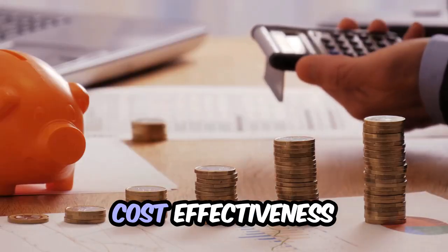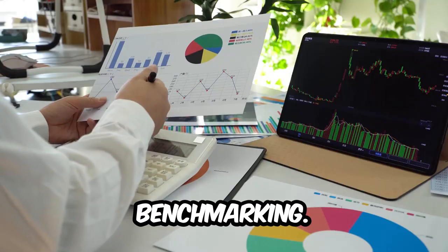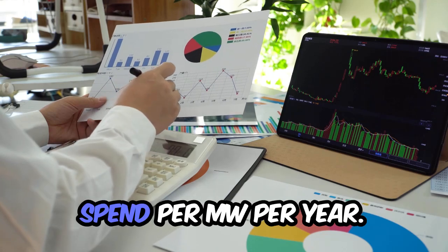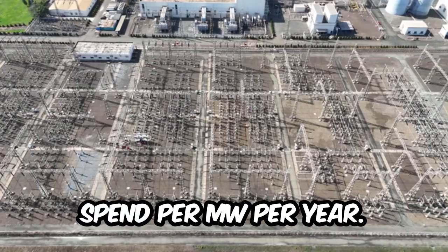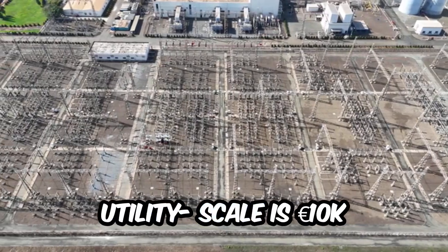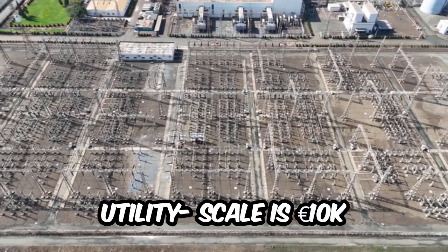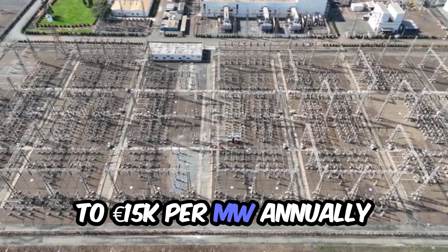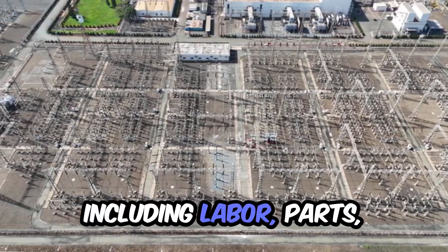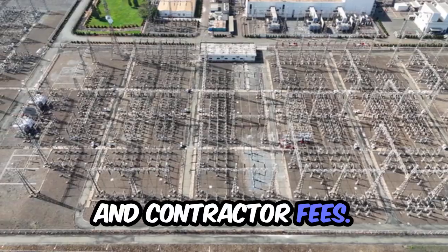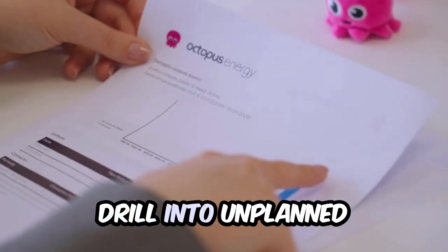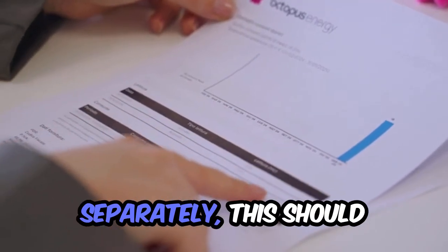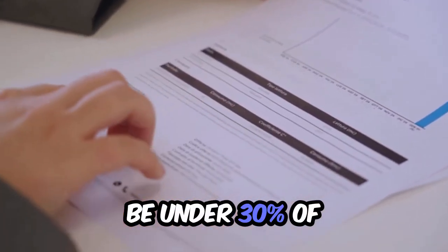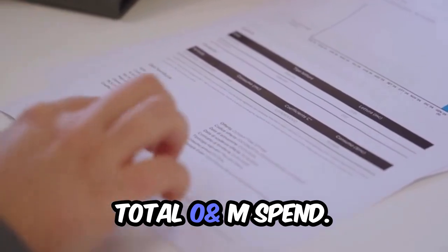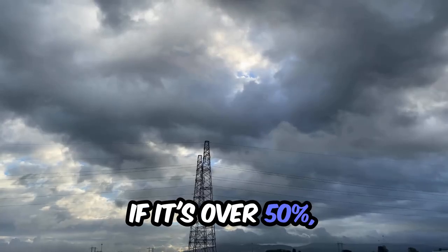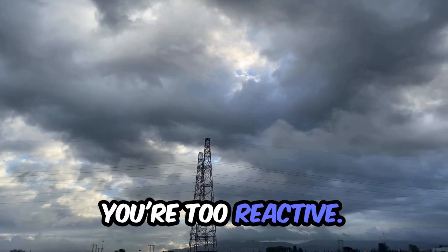Week three, cost effectiveness benchmarking. Calculate your total O&M spend per MW per year. Industry benchmark for utility scale is €10K to €15K per MW annually, including labor, parts, and contractor fees. Are you above that? Drill into unplanned maintenance costs separately. This should be under 30% of total O&M spend. If it's over 50%, you're too reactive.